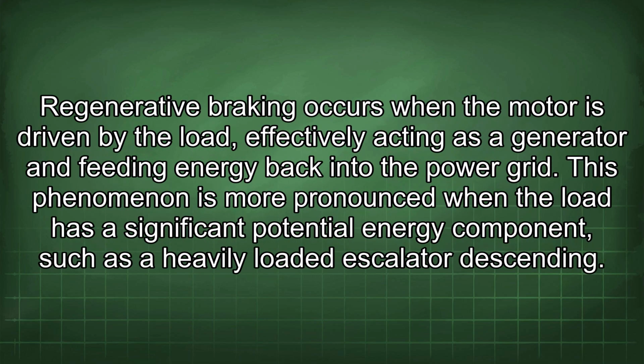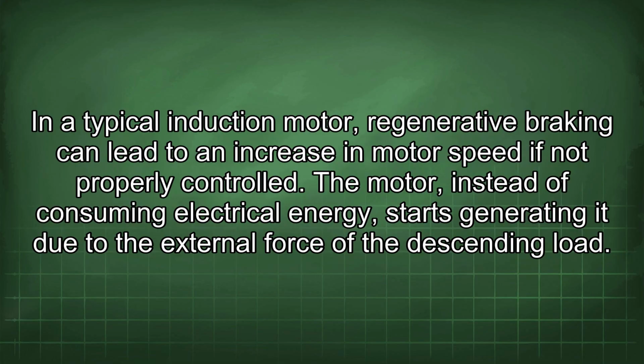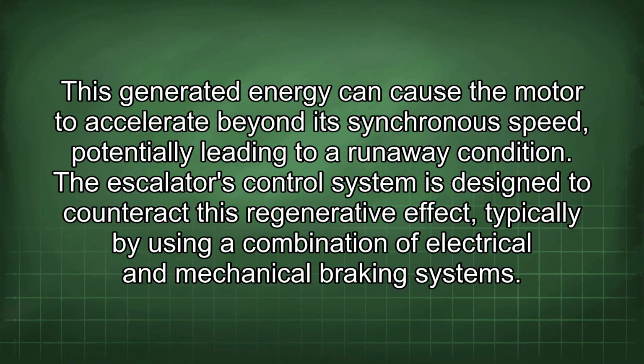Regenerative braking occurs when the motor is driven by the load, effectively acting as a generator and feeding energy back into the power grid. This phenomenon is more pronounced when the load has a significant potential energy component, such as a heavily loaded escalator descending. In a typical induction motor, regenerative braking can lead to an increase in motor speed if not properly controlled. The motor, instead of consuming electrical energy, starts generating it due to the external force of the descending load. This generated energy can cause the motor to accelerate beyond its synchronous speed, potentially leading to a runaway condition.